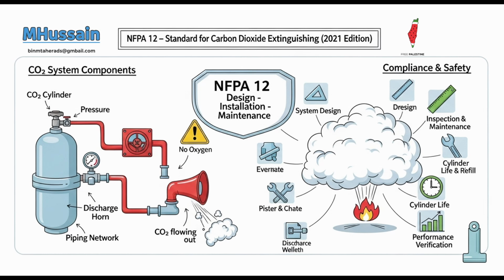How much CO2 do these need? Regarding CO2 requirements, the quantity stored must be sufficient to permit at least 1 minute of continuous use per hose line. 1 minute of spray time. The standard also makes provisions for inexperienced personnel, acknowledging that the actual users might not be expert firefighters, so the supply needs to be robust enough for them to be effective under stress. Assume non-experts might use it, so give them enough agent.